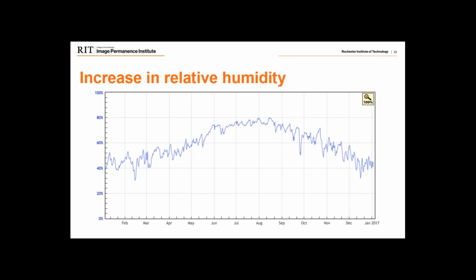But here we're starting to get very close to 80%, and so again, like we mentioned before, it's putting us pretty solidly at risk for mold germination, metal corrosion, and such. An increase in relative humidity, again, is going to be a result of one of your other two parameters. So in this instance, we definitely want to check our dew point. If we see that it's following closely with the outside air, if we don't have a mechanical system, we may have limited options, and we would want to address any moisture issues that we can in the space, whether that's redirecting gutters or fixing leaks, and we would potentially want to look at increasing the heating to the space to try to lower that relative humidity.